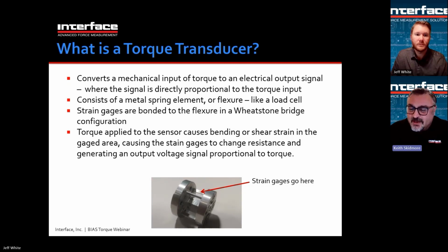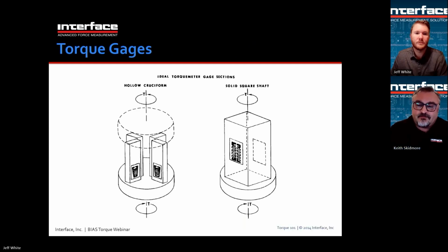So the output inherent in any of the torque sensors that we are going to talk about today are millivolt per volt outputs, and then any different kind of signal that may come out of the torque sensor would be due to some type of processing. But inherently, the basic measurement device is a strain gauge based sensor. Next slide. So basically, you can have a square shaft or a solid round shaft.